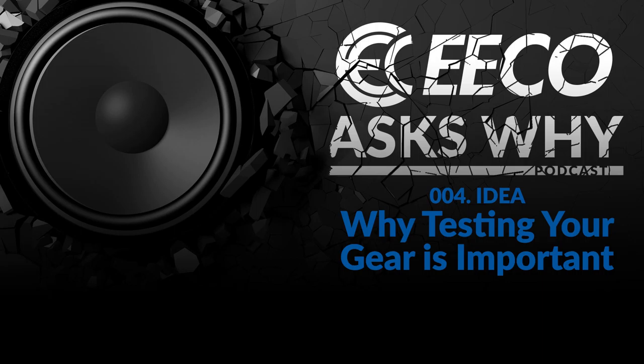Is it tripping quickly, as soon as it energizes, tripping immediately, or is it tripping over time? There are two different ways that a breaker operates. It'll operate what's called instantaneously, which means that if a breaker sees a short circuit somewhere, it will trip immediately. You will try to close the breaker, and it will immediately trip. That is a good indication that you might have a shorted cable. You might have a shorted motor lead. You might have some failure that should be easily detectable downstream.